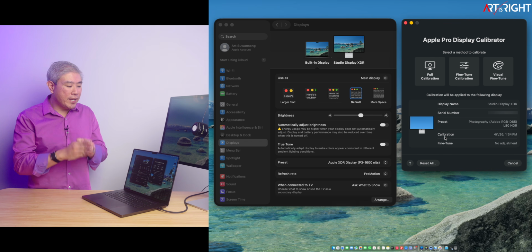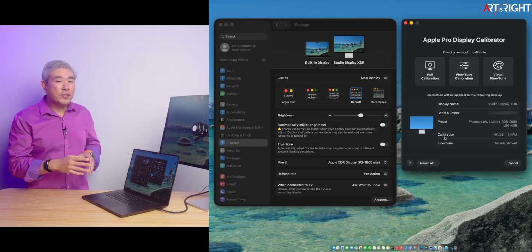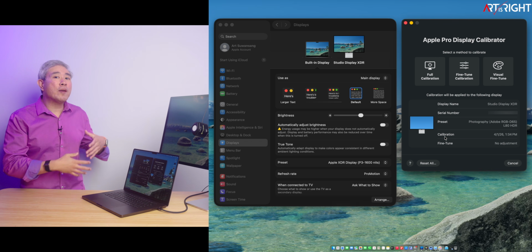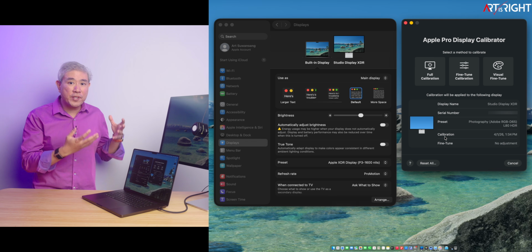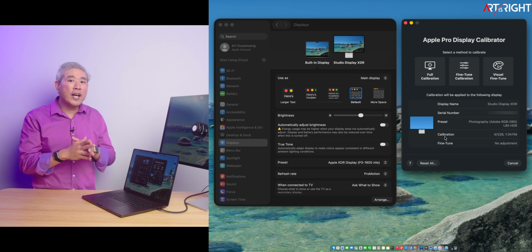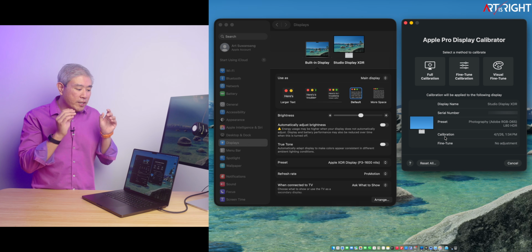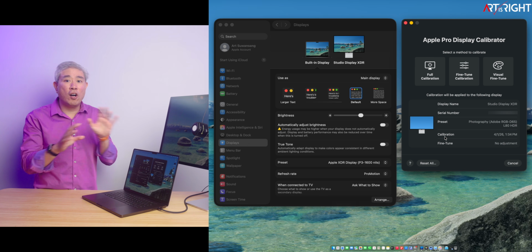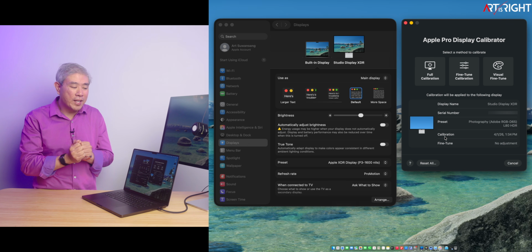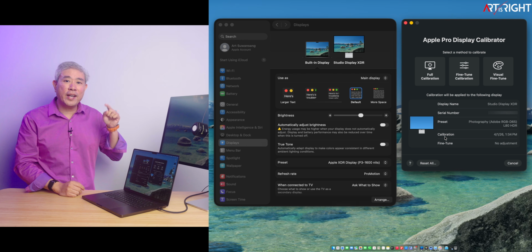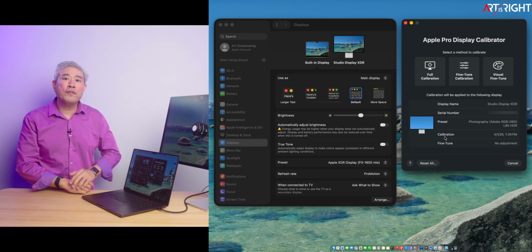Right below that is fine tune. So fine tune right now says no adjustment. And even though I may have done fine tuning on this specific preset before, a full calibration would remove the fine tuning, not just only on this preset, but on all the presets that you have on your display. This is where you watch my part 2 video and follow through that guide on how to fine tune the calibration again.